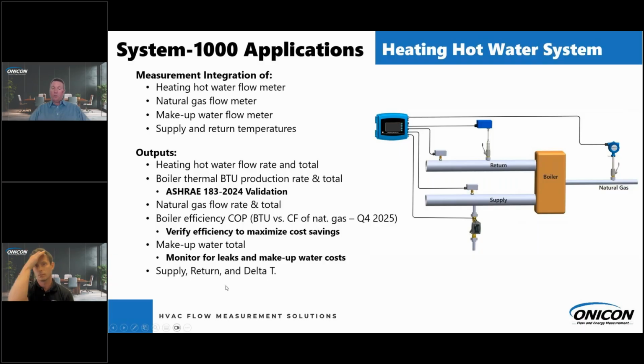And coming in Q4 of 2025, you'll be able to do boiler efficiency COP, where we're measuring the BTU generated by your boiler versus the cubic feet of natural gas being taken into the system. So again, you can verify the efficiency of your system and you can maximize your cost savings with that. Again, we'll also be able to do a makeup water total for you there, so you can monitor for leaks and measure your makeup water costs. And again, we'll also have the outputs of supply, return, and delta T.